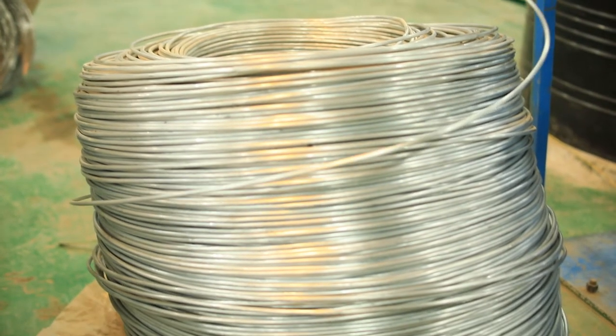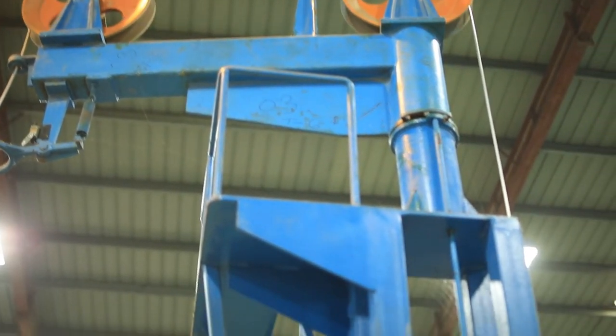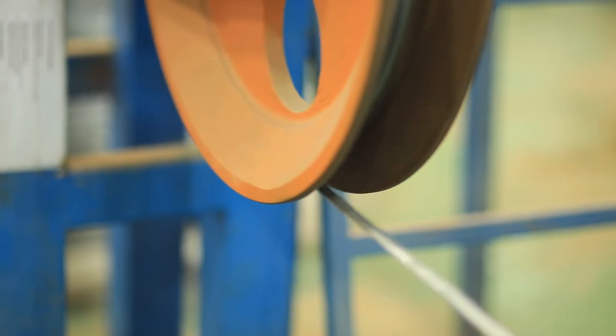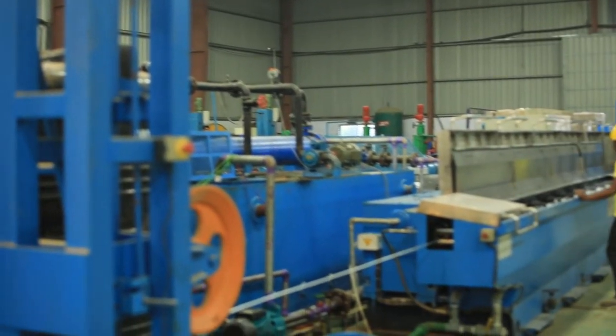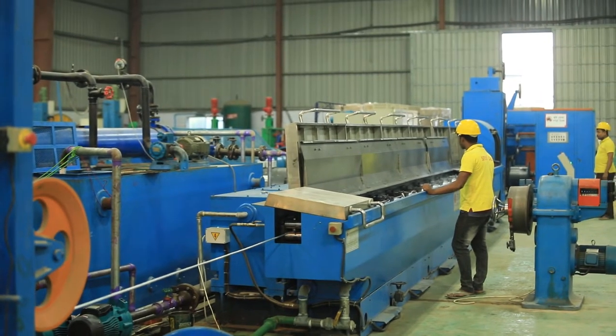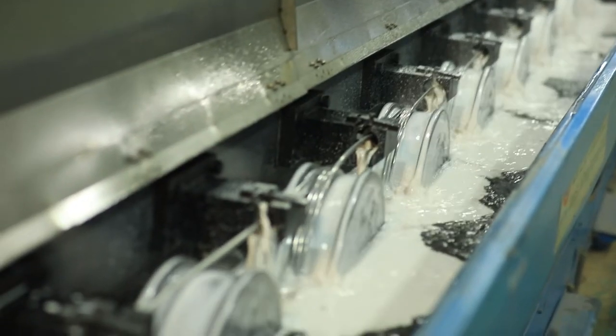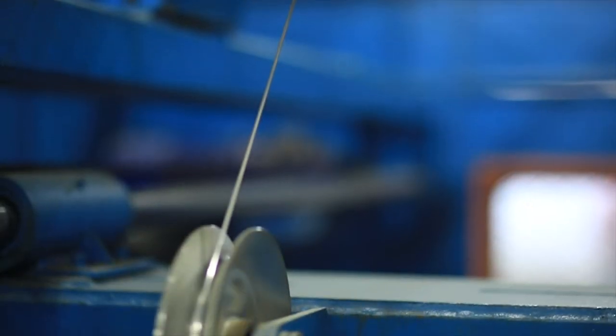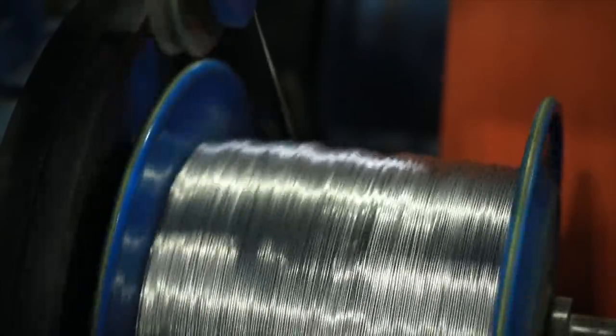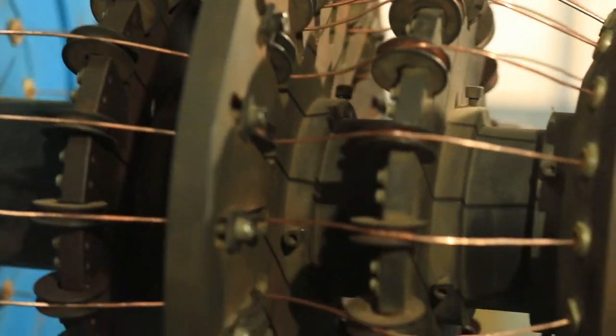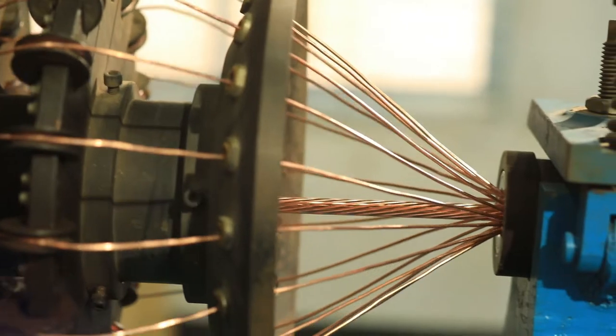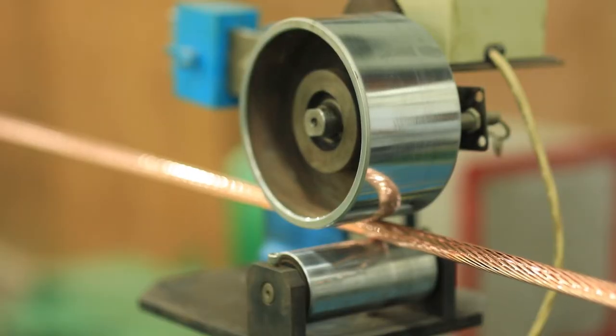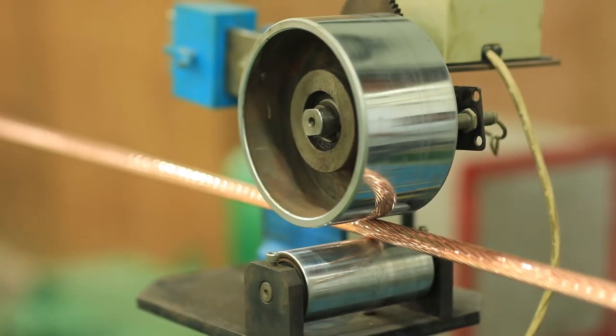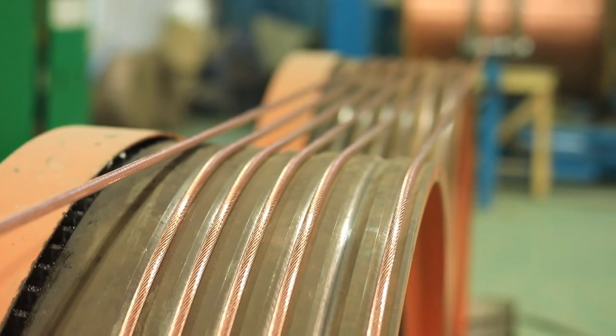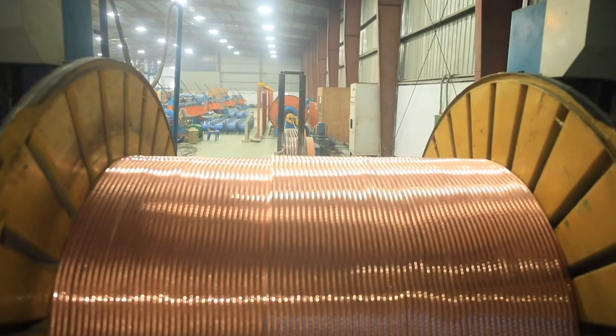The plant is capable of drawing wire from 8mm to 0.1mm sizes. The wires are ensured with quality in all stages of the drawing process. These drawn wires are then stranded to achieve the conductor as per specifications. Conductors are formed on a high-speed stranding machine and then compacted to ensure reduction of AC losses. To ensure optimum performance, extensive focus is paid to the conductor resistance and shape.